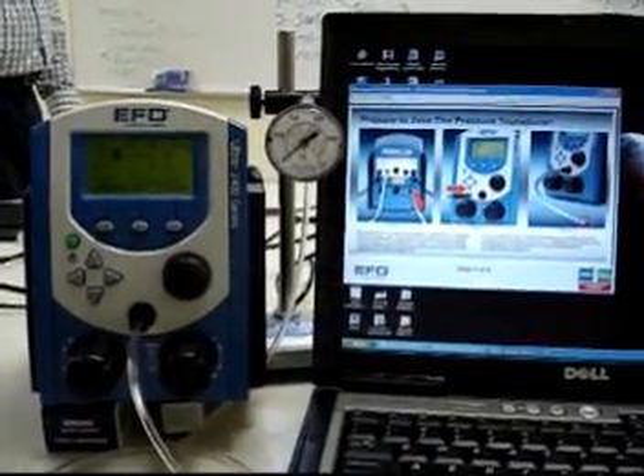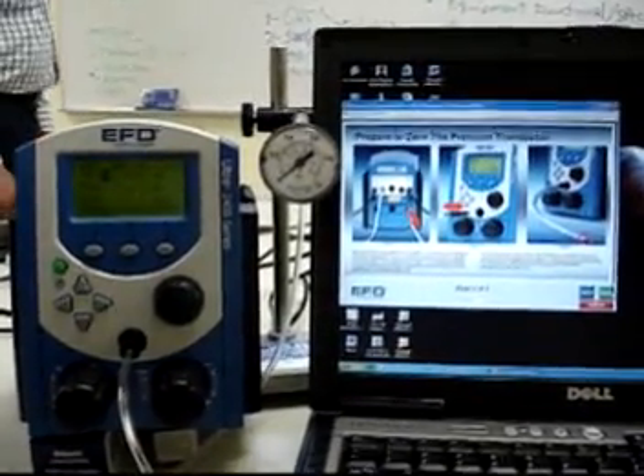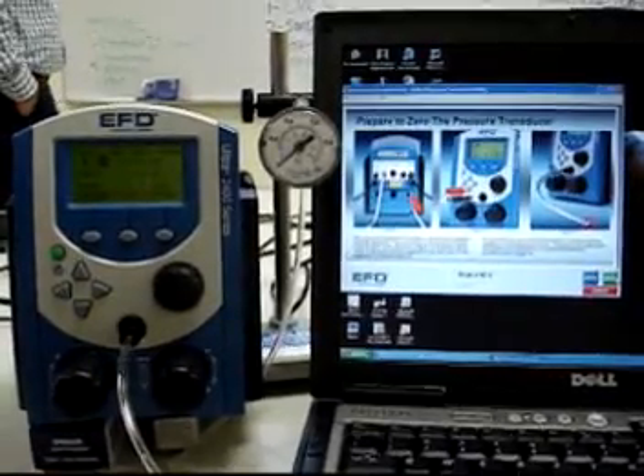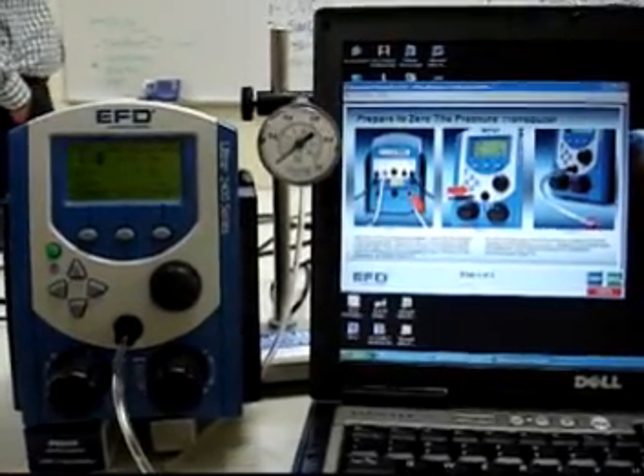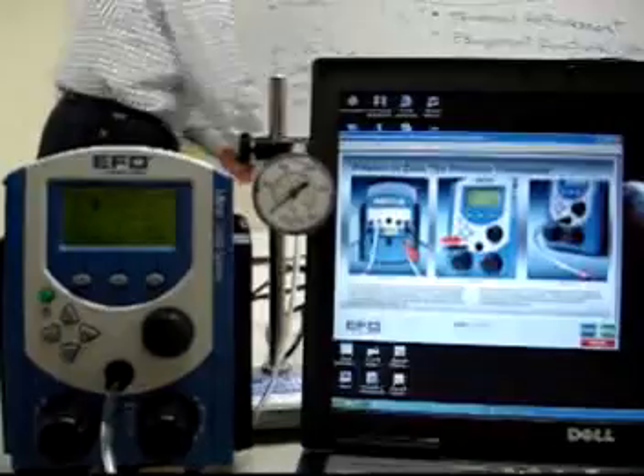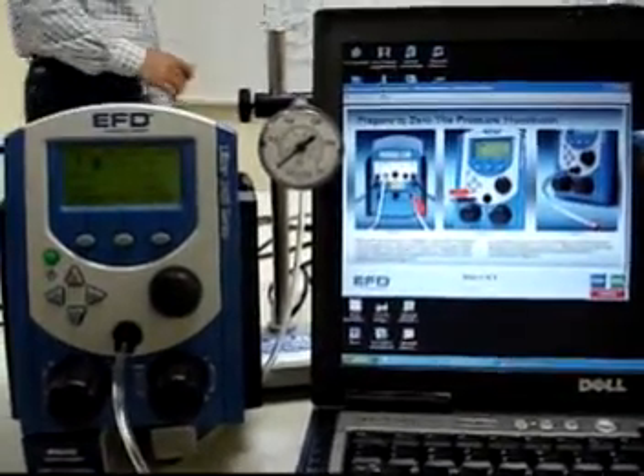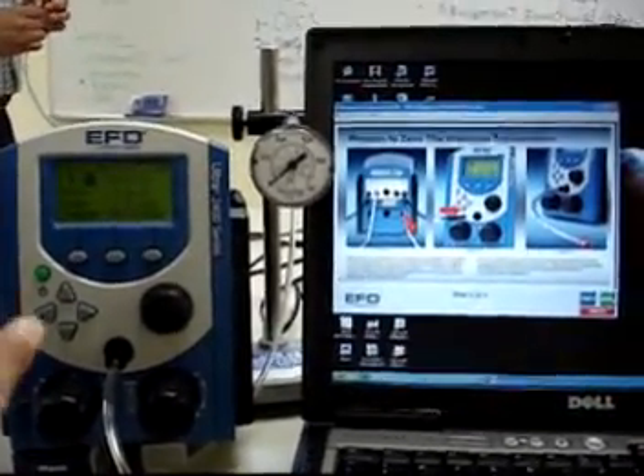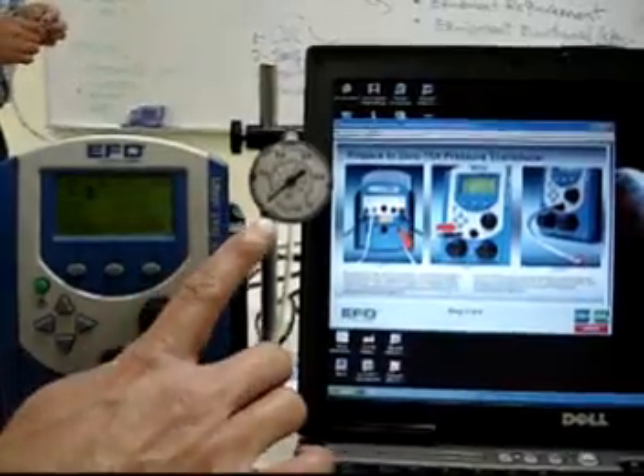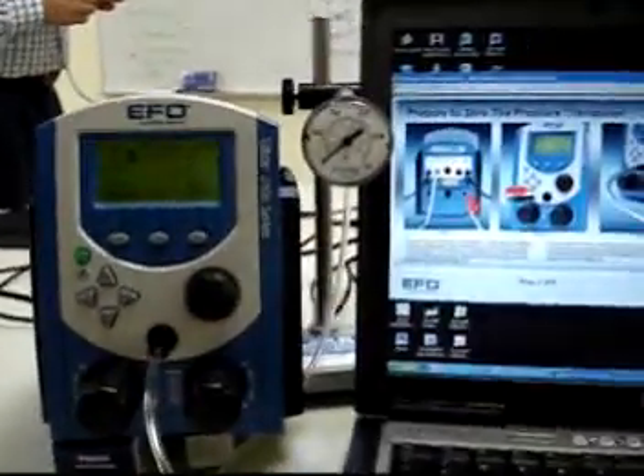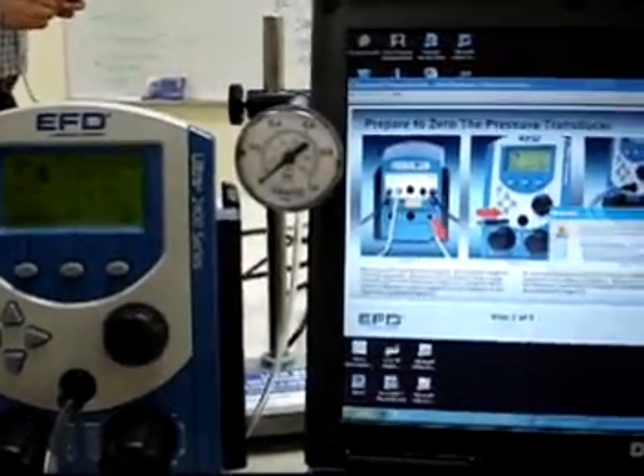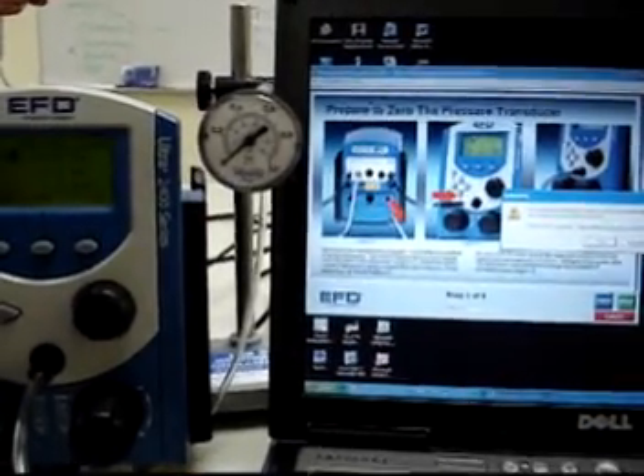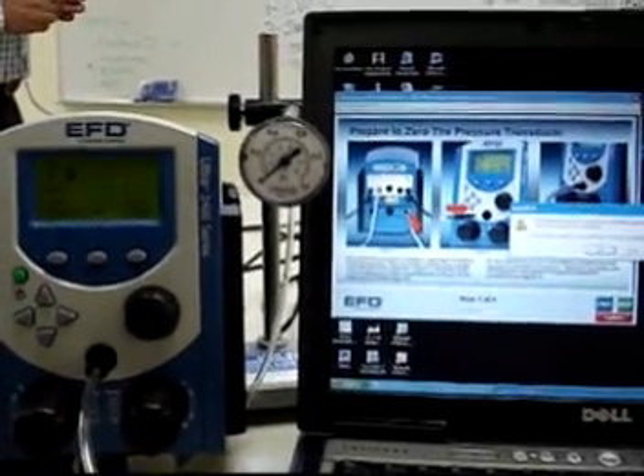Okay, we're ready to calibrate on zero pressure the transducer, and we're about to disconnect the air. Let's disconnect the air. There is no air right now. We have 0 psi in the machine and 0 psi on my calibrated gauge. Then I click next. It says the pressure transducer is going to be zeroed.